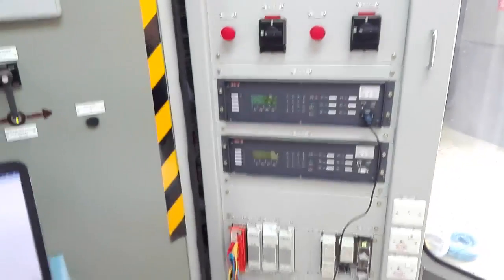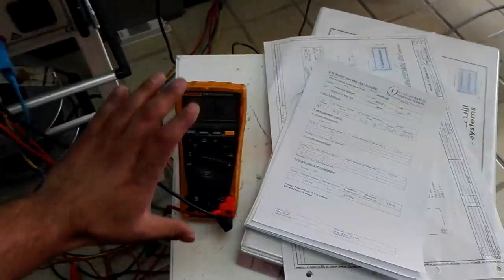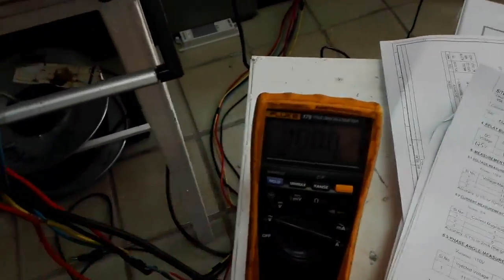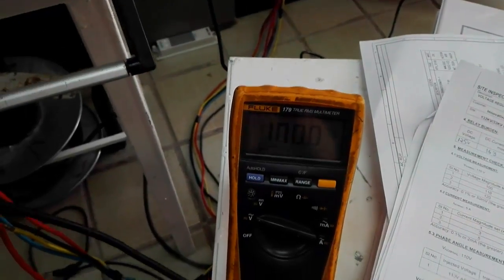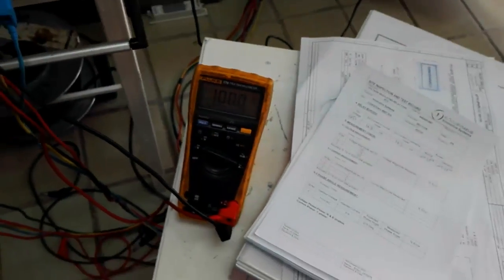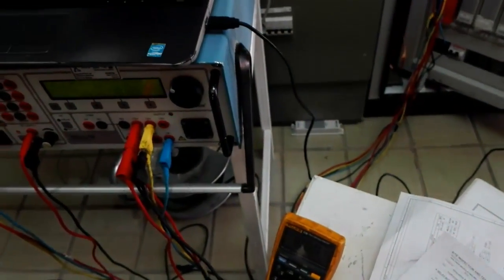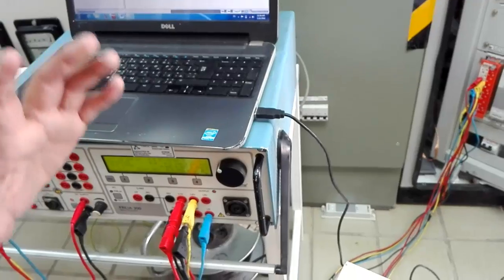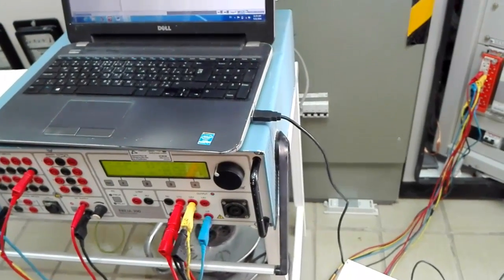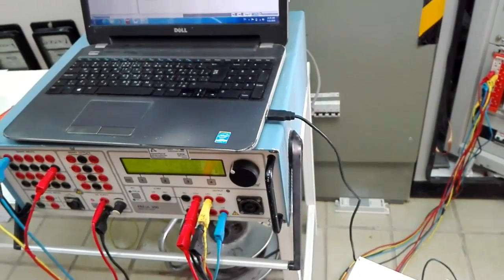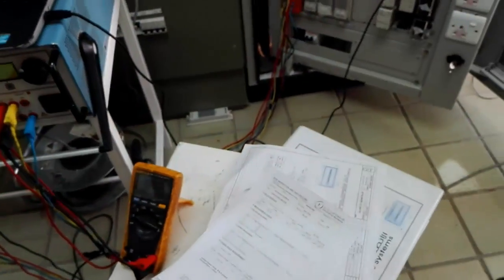93.46. Why this? We will explain this point, because we have involved three equipments here: our ZIV relay, then the Freja box, and then our multimeter. So better is to avoid more equipments. It will minimize our error. If we would have used our Freja directly, it would have given us around 99.98 or 97.95, something like this.